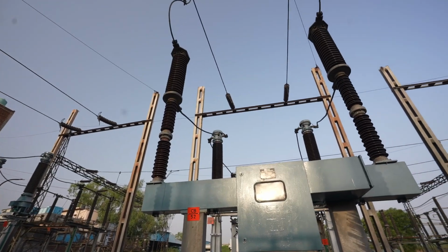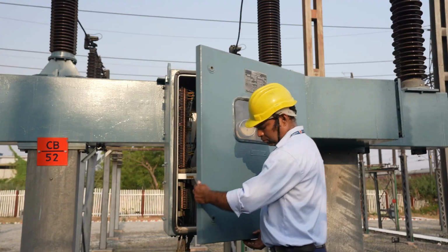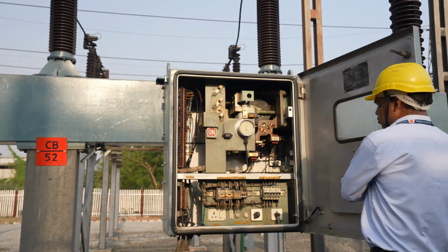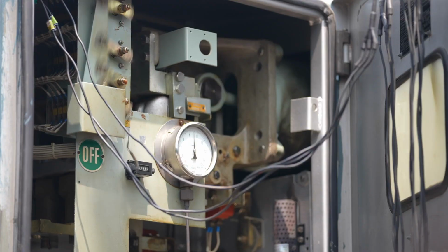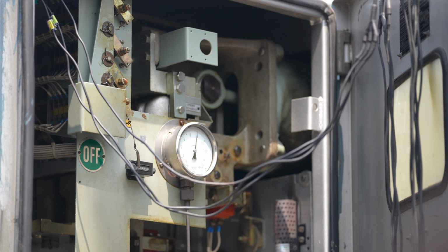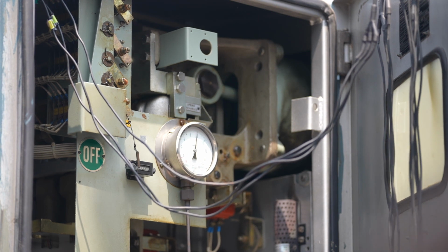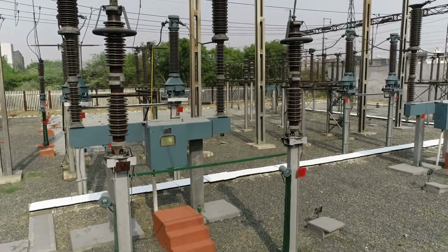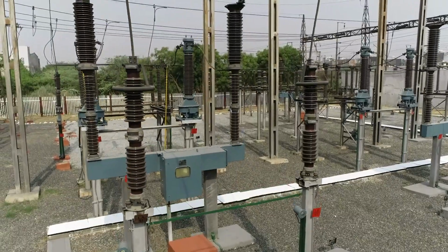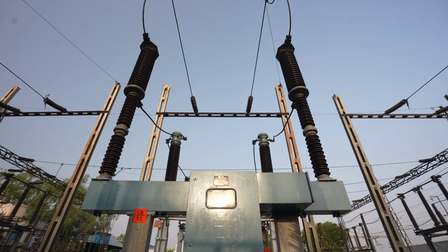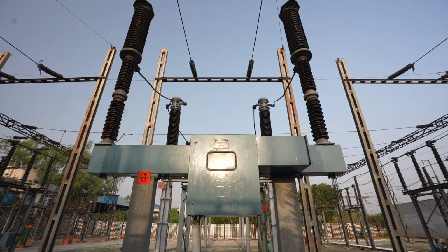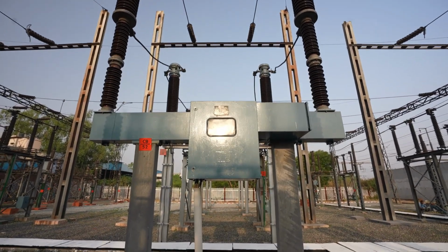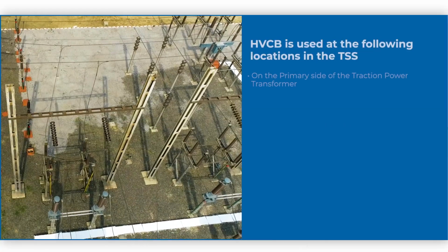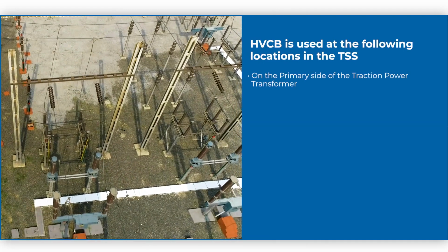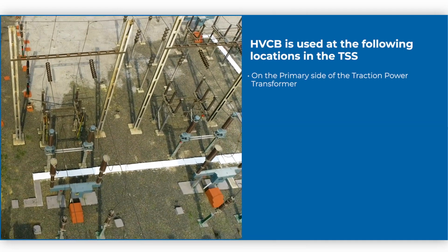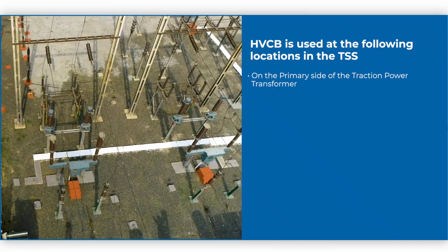SF6 circuit breaker, HVCB, is a protective device to connect or disconnect the power supply to the circuit during normal and any abnormal condition occurs in the circuit. SF6 CB uses pressurized sulfur hexafluoride gas, SF6, to extinguish the arc due to its superior insulating and arc quenching properties. HVCB is used on the primary side of the traction power transformer in the TSS for protection.